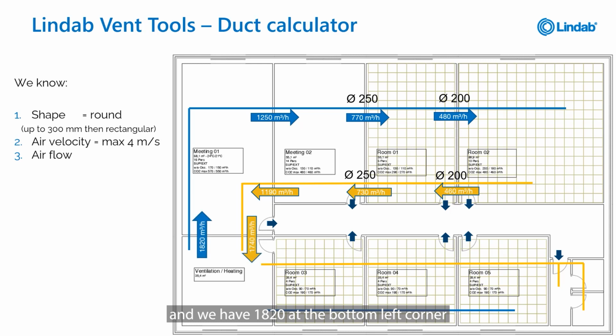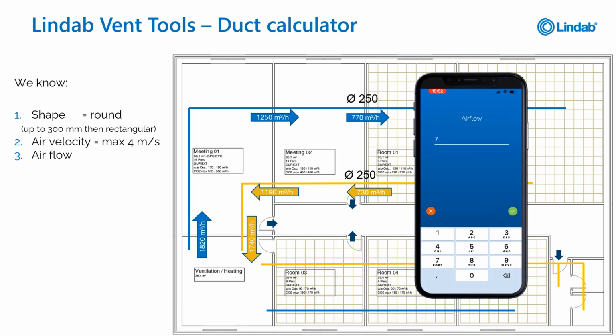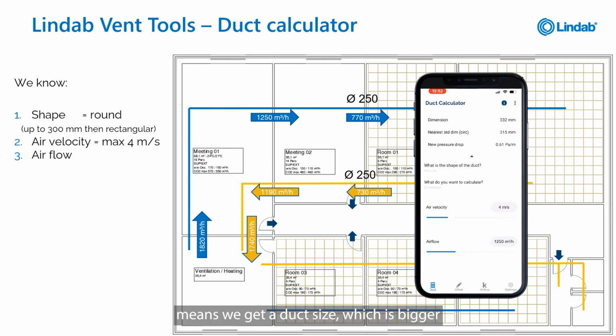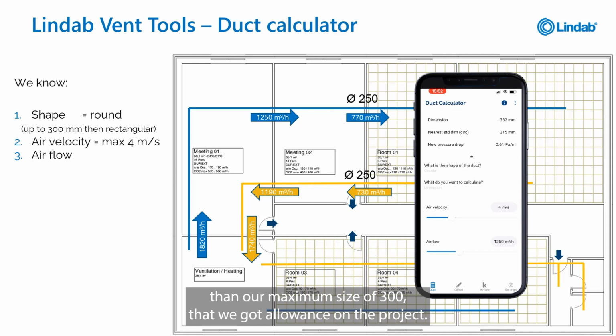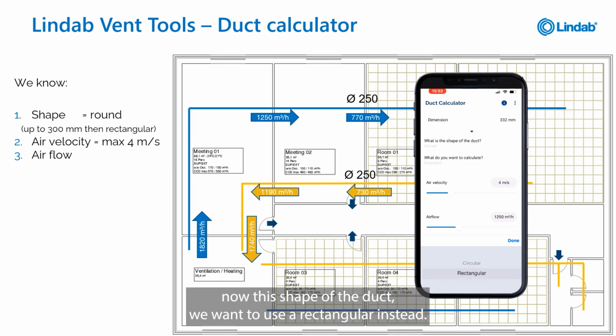Now we come to the next level, which is 1250 in supply at the next corner, and we have 1820 at the bottom left corner. Just using these two values, typing in the 1250, means we get a duct size which is bigger than our maximum size of 300 that we are allowed on the project. So therefore, we now change the shape of the duct.